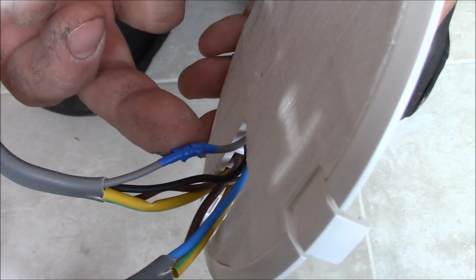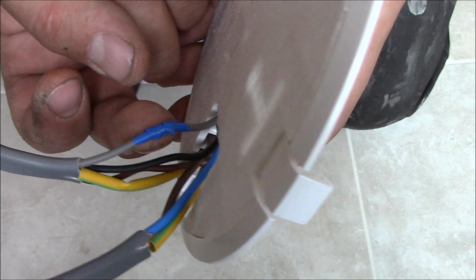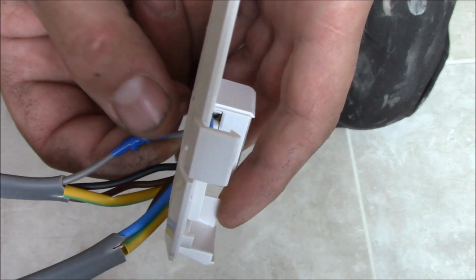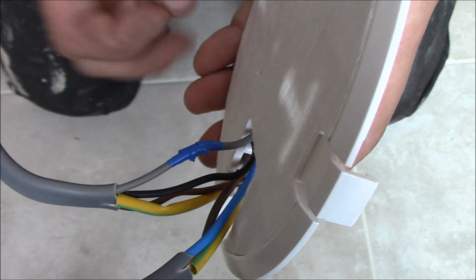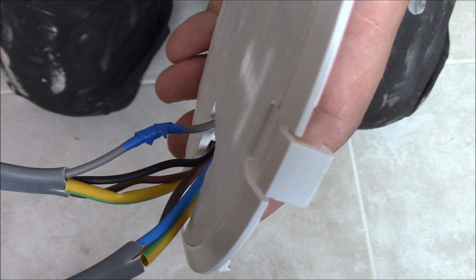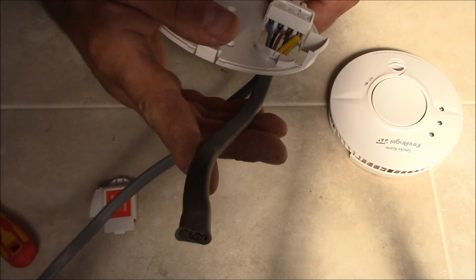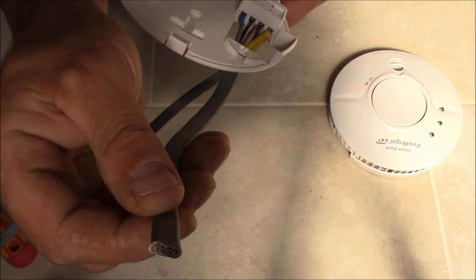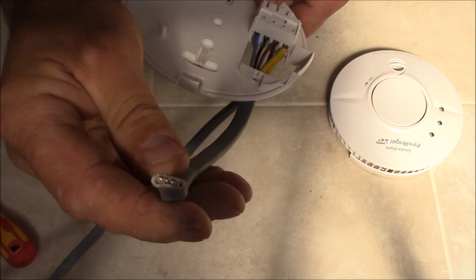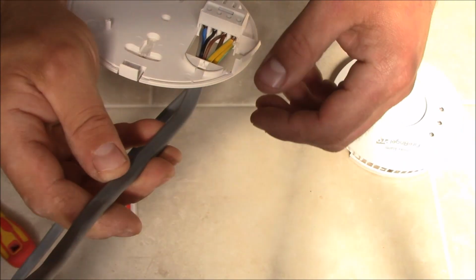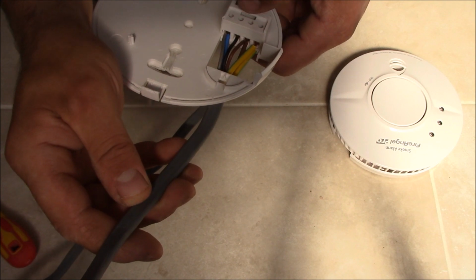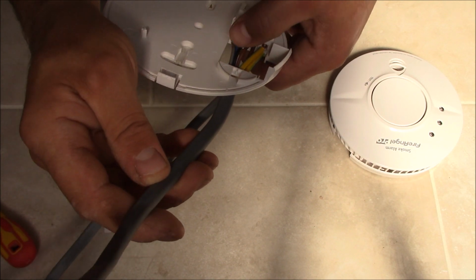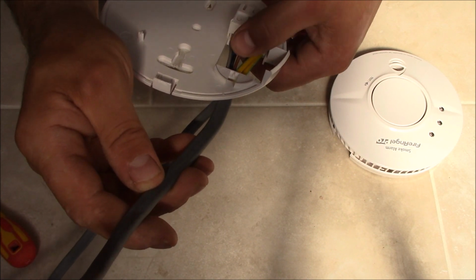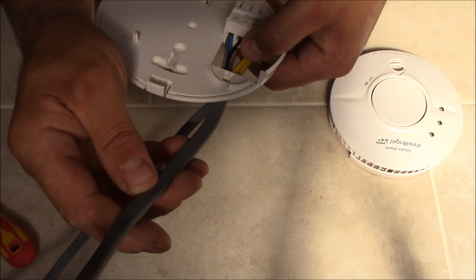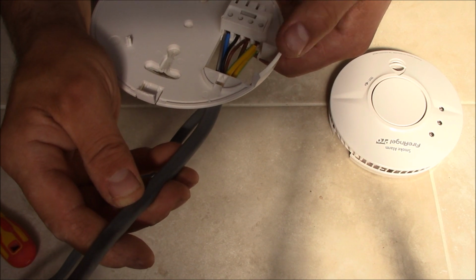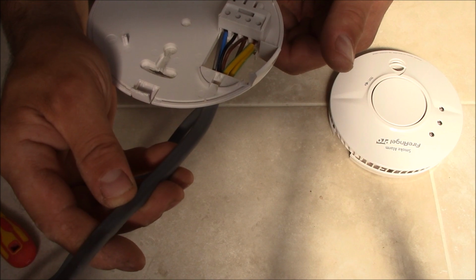And also on the grey wire you need to put blue sleeve or blue tape on it, to indicate that this is neutral. And obviously on the other end of the 3-core and earth cable you connect another smoke alarm exactly in the same way as here. So basically grey to neutral, black to interconnection, brown to live, and earth to earthing terminal.